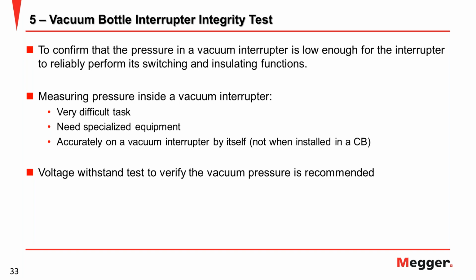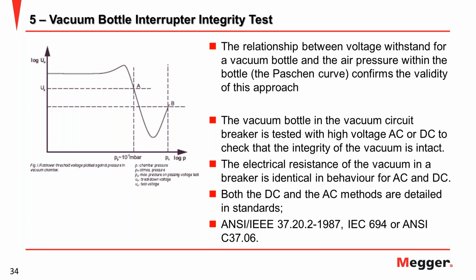Because of these difficulties, we can use the voltage withstand test to verify vacuum pressure. There is a relationship between vacuum pressure and the withstand voltage test based on the Paschen curve. You see, this is the Paschen curve, the relationship between withstand voltage for the vacuum bottle and the air pressure within the bottle.